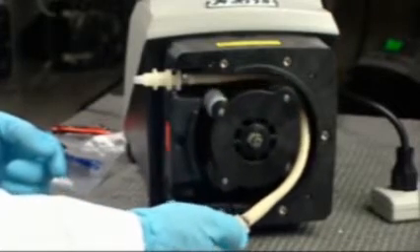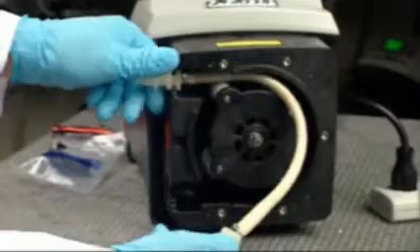Grasp the inlet pump tube fitting and pull the fitting straight out of the pump head. Allow the pump tube to automatically walk its way out of the pump head. Grasp the outlet pump tube fitting and pull the fitting straight out of the pump head. Press the stop button.